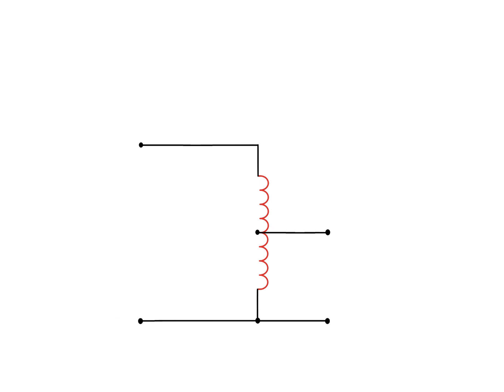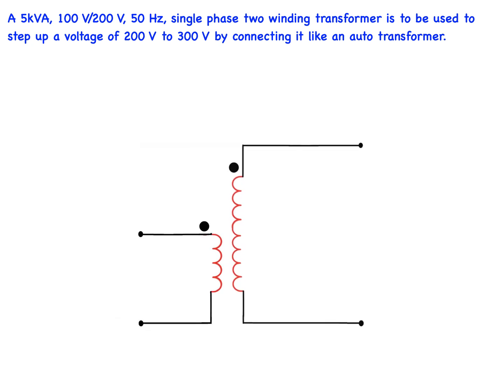Autotransformers are cheaper than a similarly rated two-winding transformer when the voltage transformation ratio is close to unity. A single-phase two-winding transformer, though, can be suitably connected to perform like an autotransformer. In this example, a 5 kVA 100 volt to 200 volt 50 Hz single-phase two-winding transformer is to be used to step up the voltage from 200 volts to 300 volts by connecting it like an autotransformer.